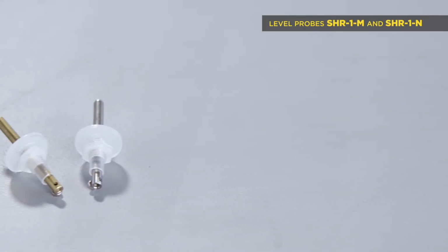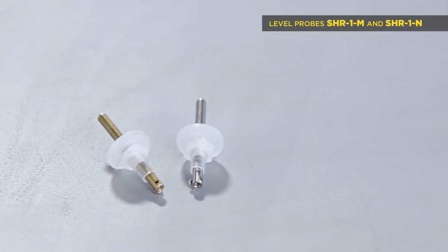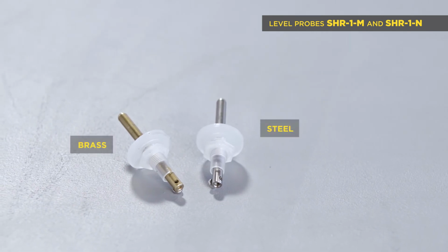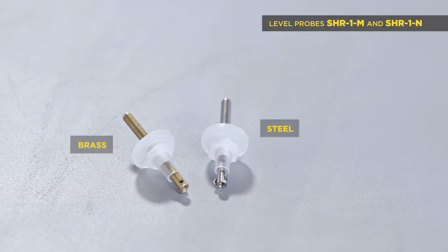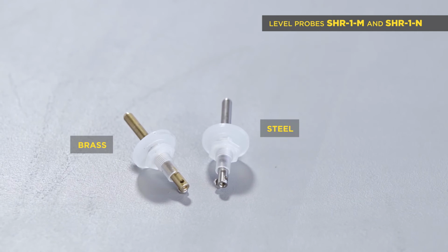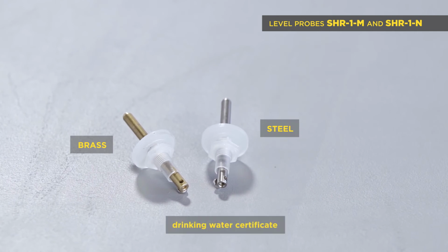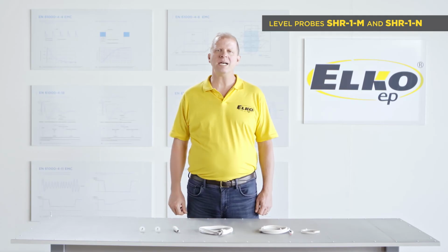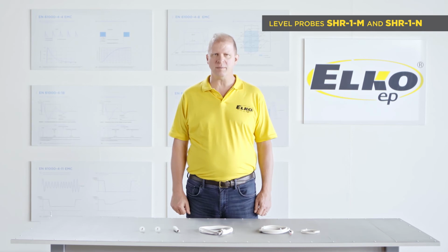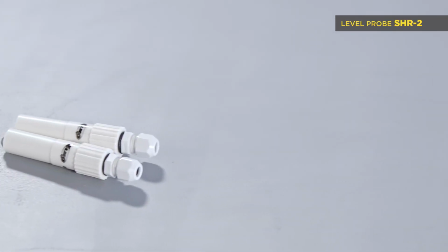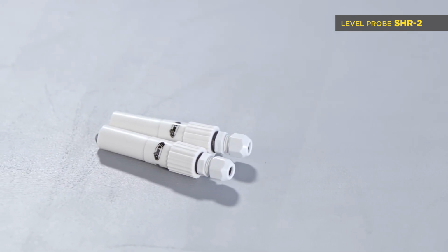Let me show you level switch accessories. Probes: SHR1M brass and SHR1N stainless steel probes. Electrodes with a diameter of 4 millimeters in a plastic cover are suitable for drinking water. The wire has a maximum profile of 2.5 millimeters squared. SHR2. This is a stainless steel electrode in a plastic cover with gland PG7.